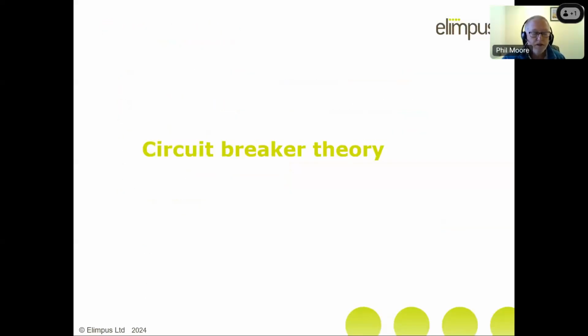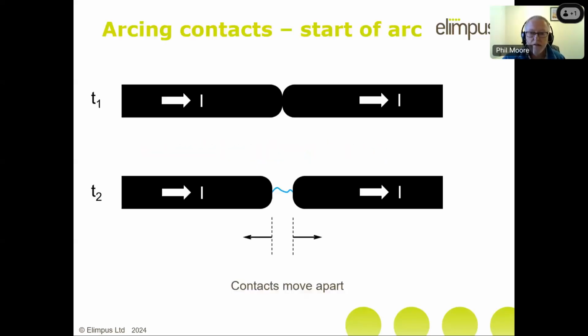So a little bit about circuit breaker theory. Circuit breakers essentially contain contacts which can produce an arc. I'm not trying to show you a very accurate model of what's inside a circuit breaker. I'm just trying to elucidate the essential details so that you'll understand why we're monitoring the way that we are. You can imagine the top graphic is showing you two contacts pressed together that allow the passage of current. And if you were to separate those contacts, then you would end up with an arc between them. I've shown here both of the contacts moving.